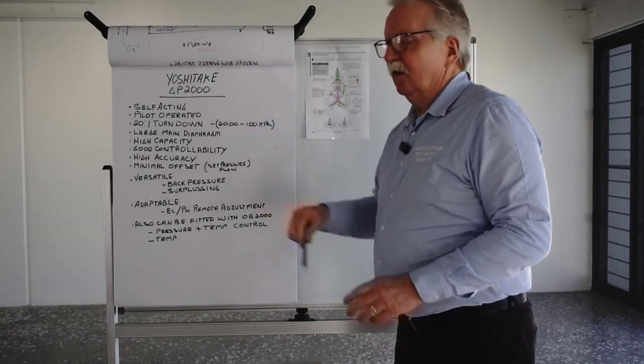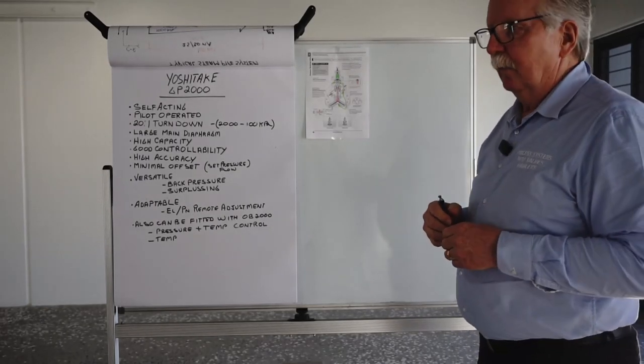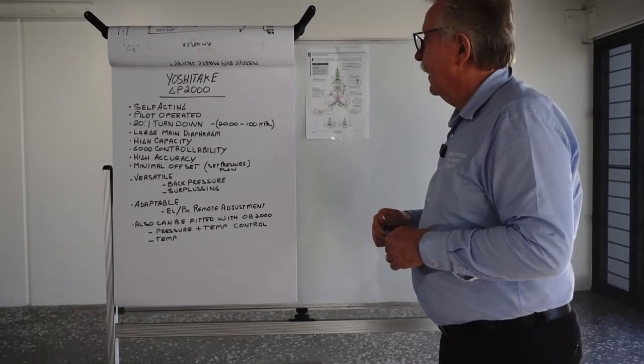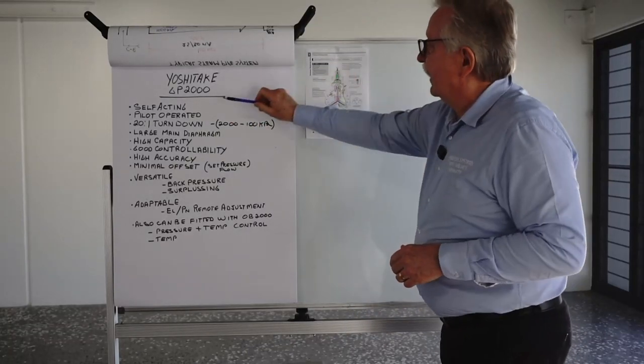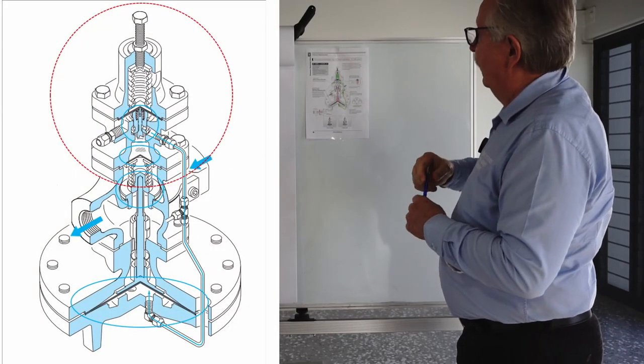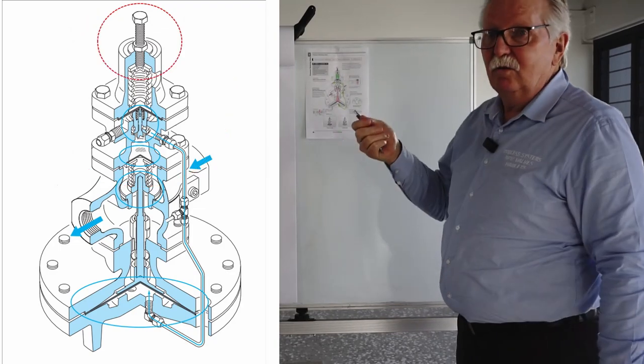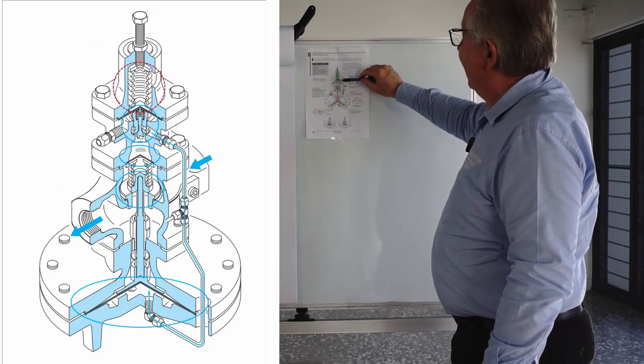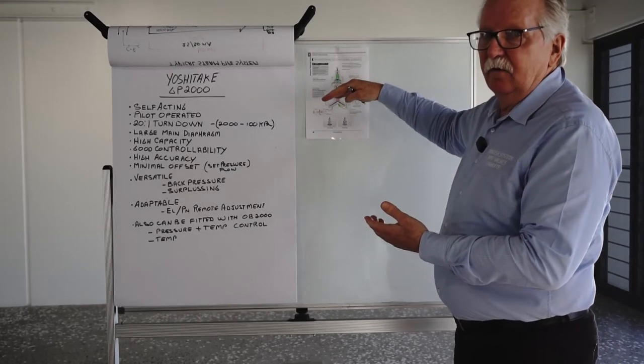The GP2000 is a self-acting unit. That means you don't need any external source of motivation either in pneumatics or electrics to get it to operate. It's pilot operated. Now the self-acting and the pilot operated can be identified in this area here of the pressure reducing valve. Basically there's an adjusting knob on the top which you use a spanner to adjust. And you adjust that against the spring tension. And that is how you will adjust your pressure up and down due to the way the valve operates.